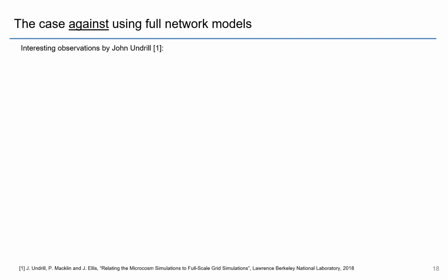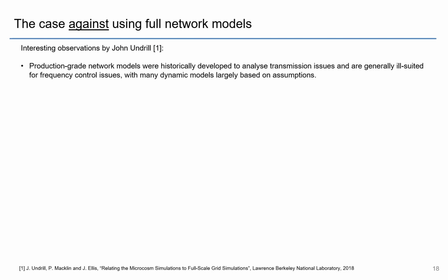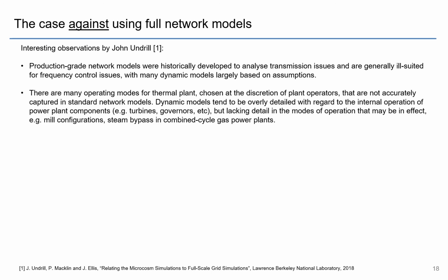John Undrill made some interesting observations regarding the use of full network models. It is that production-grade network models were historically developed to analyze transmission issues and are generally ill-suited for frequency control issues. And many of the dynamic models are largely based on assumption, the parameters, that is. There are many operating modes in the thermal plant, and they're chosen at the discretion of plant operators, and they're not accurately captured in standard network models. So the work goes on to say that dynamic models tend to be overly detailed with regard to the internal operation of power plant components, such as the turbines and the governors, but they're lacking in detail in the modes of operation that may be in effect. And we've seen this as well with coal-fired power plants in terms of their mill configurations, or combined cycle gas plants in terms of running steam bypass.